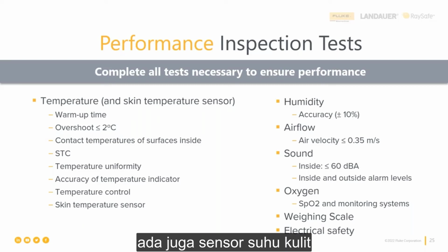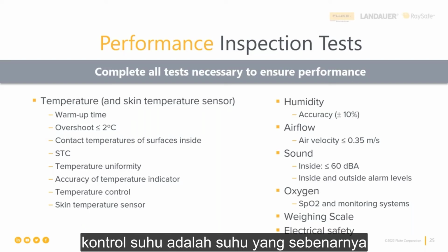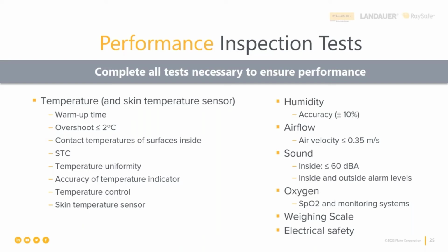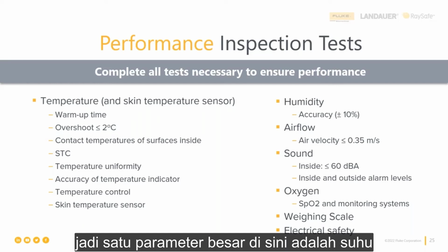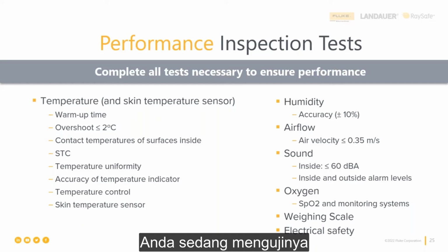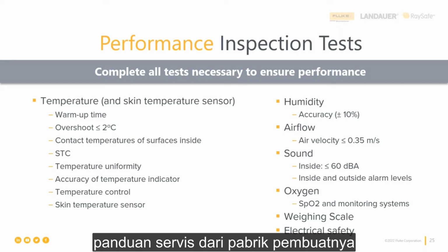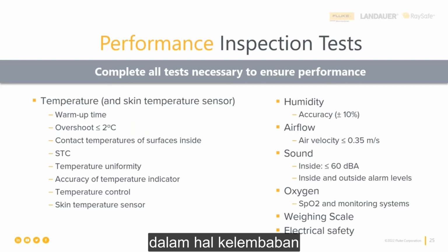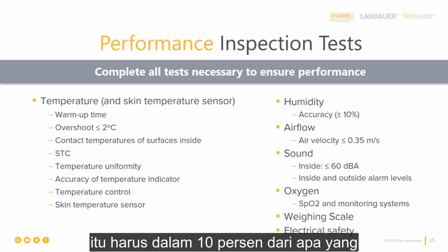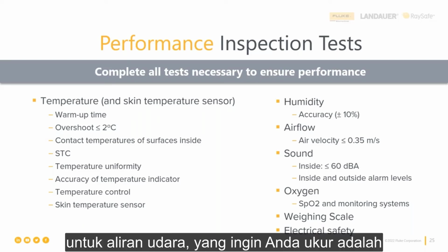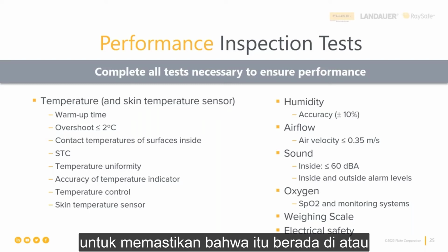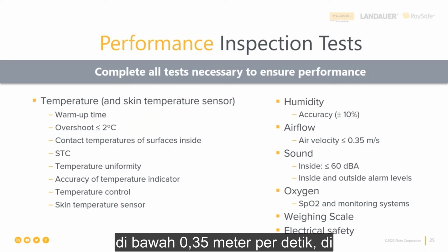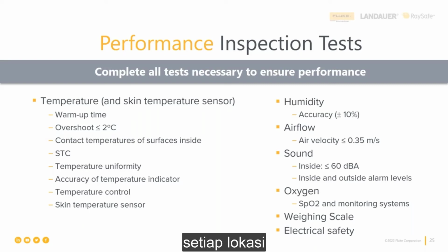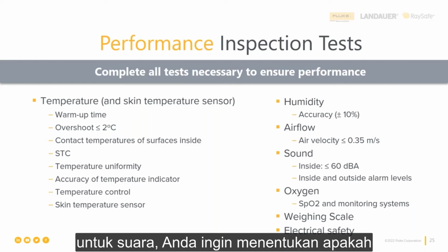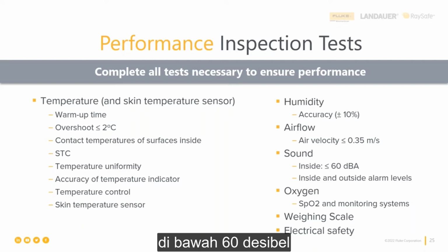There's also a skin temperature sensor, and you want to test that with a calibrated heater assembly. And you want to test to ensure that the temperature control is the actual temperature sensed by the skin temperature probe. So one big parameter here is temperature, and there's a lot to go through when you're testing it. So do refer to either the standard or the manufacturer's service manual. In terms of humidity, you want to check the accuracy of the relative humidity. It should be within 10% of what the tester indicates. For airflow, you want to measure the air velocity inside the incubator compartment to ensure that it's at or below 0.35 meters per second, again, at each location. For sound, you want to determine if the sound level inside the incubator compartment is below 60 decibels.